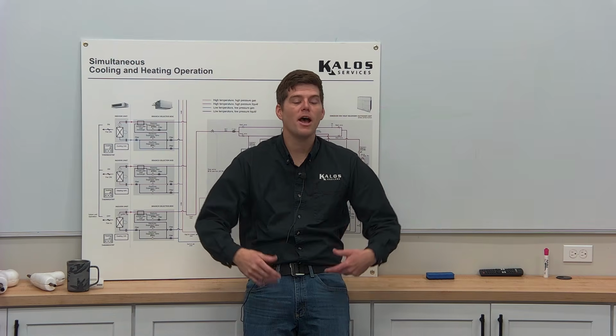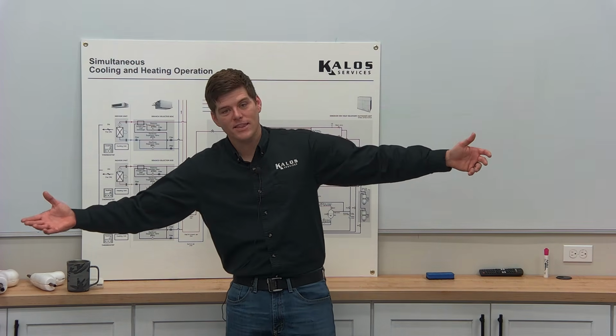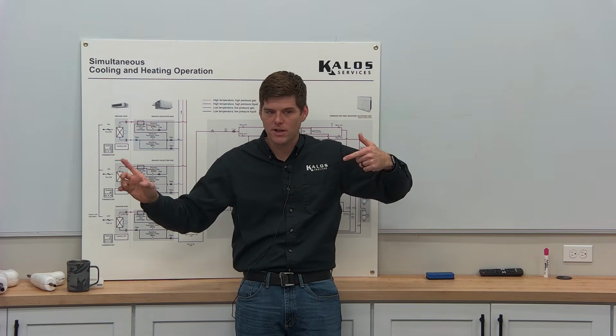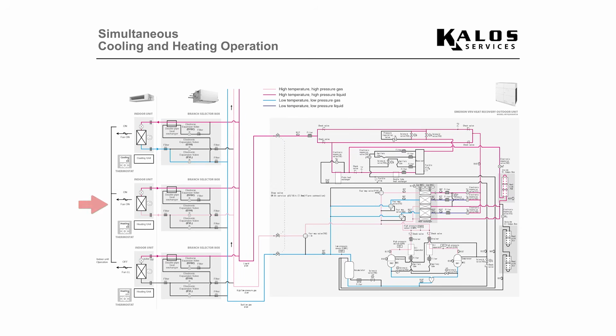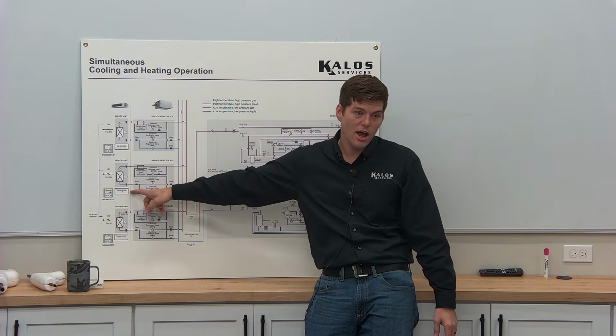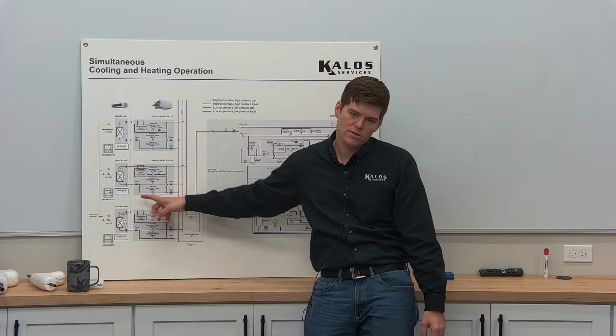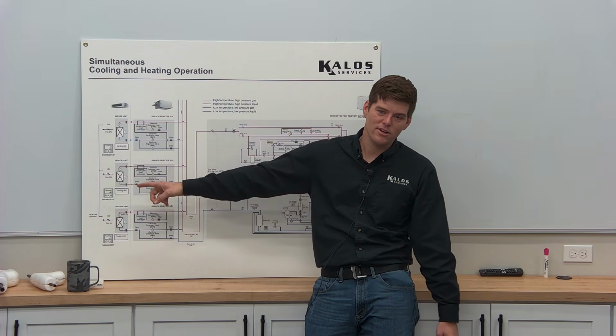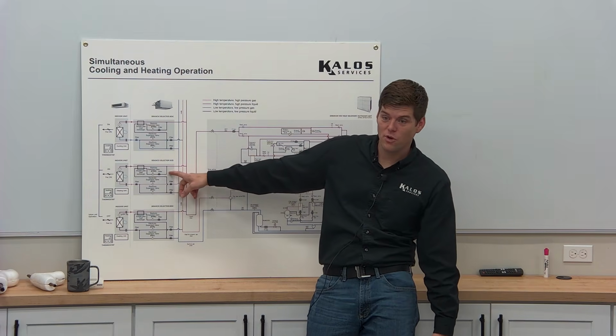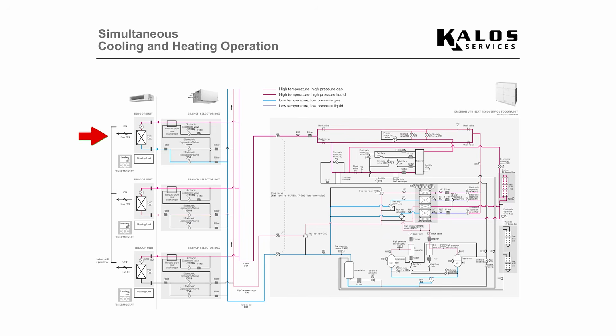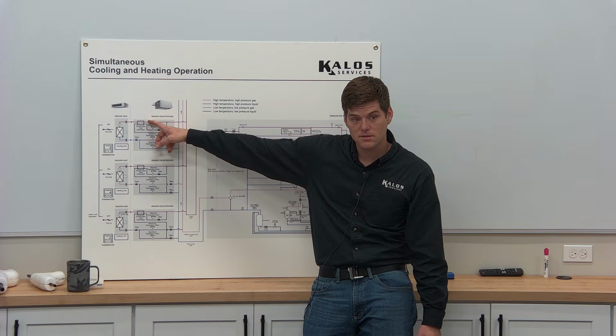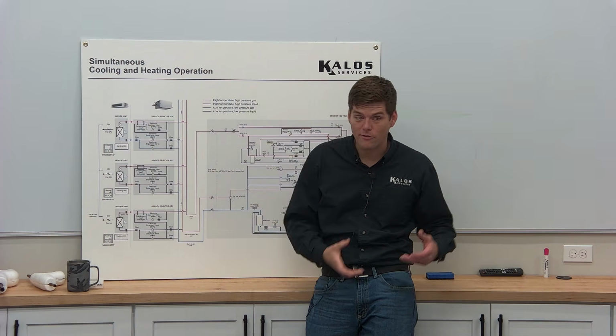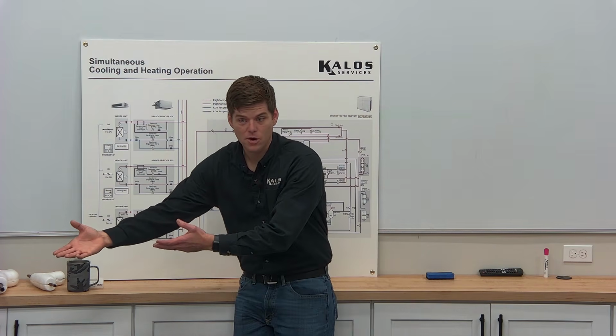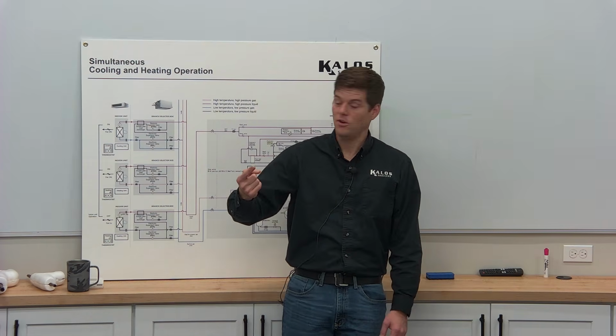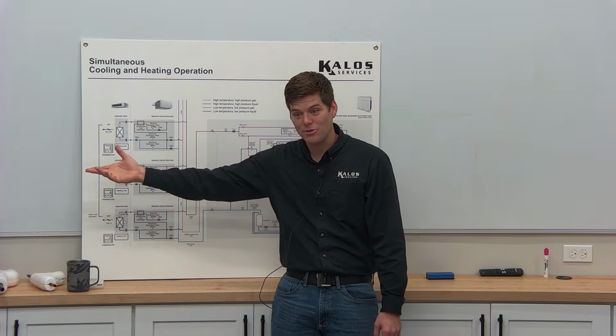Correct. Yeah. So the premise behind heat recovery, guys, the secret sauce in heat recovery that makes all of this possible, and it only goes one way, it doesn't go both ways, contrary to popular belief. We take hot gas, we give it to the indoor unit that's calling for heating. What happens when we run hot gas through an indoor heat exchanger with a fan on? What takes place? Condensing. Condensing to a what? Liquid. That liquid leaves this box. And instead of going back to the outdoor unit, where does it go? It takes a quick, short little jog to the next unit that's calling for cooling. Energy, heat, taken from this space, is then transferred to this space. That's why it's called heat recovery. We are recovering it from one space, and we are delivering it to another space without having to make another trip around the sun. Instead of going back to the outdoor unit 200 feet away and then back to the indoor unit, it literally just goes here.